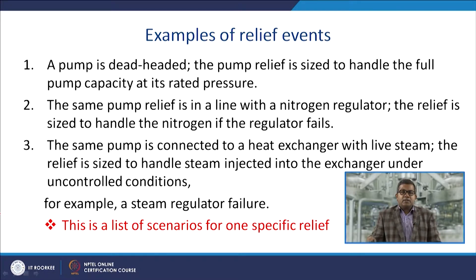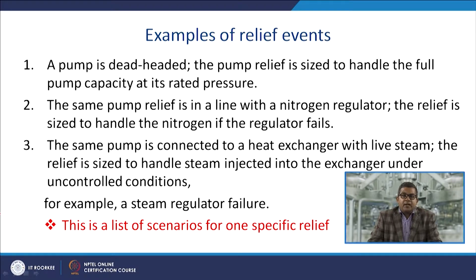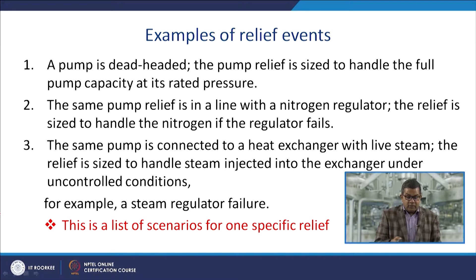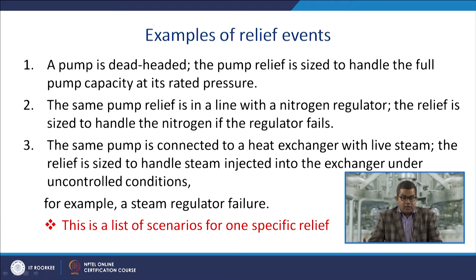Consider a pump that is dead-headed: the pump relief is sized to handle the full pump capacity at its rated pressure. If the same pump relief is in line with a nitrogen regulator, the relief is sized to handle the nitrogen if the regulator fails. If the same pump is connected to a heat exchanger with live steam, the relief is sized to handle steam injected into the exchanger under uncontrolled conditions. The pump and relief are the same, but the media differs.